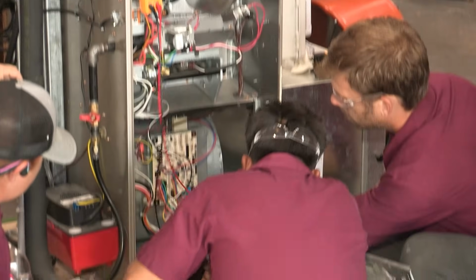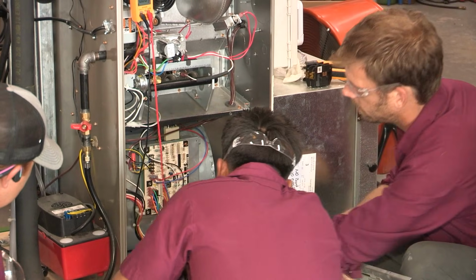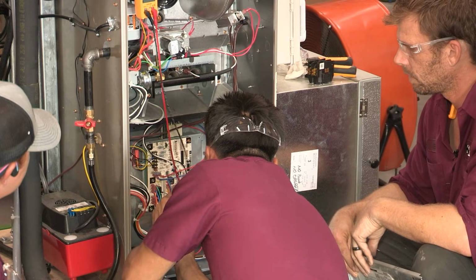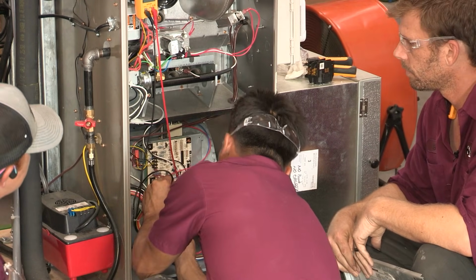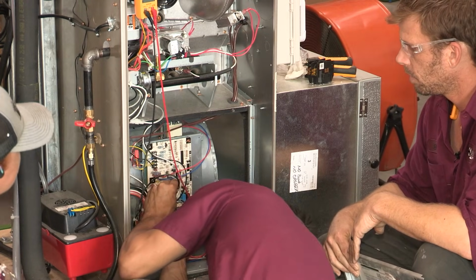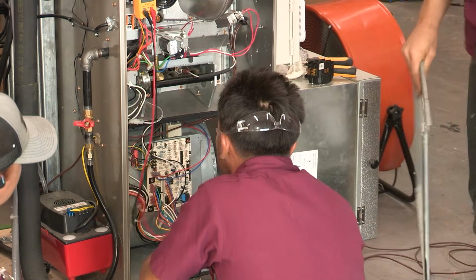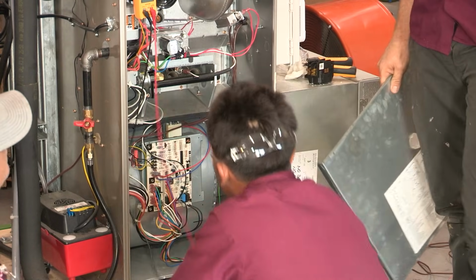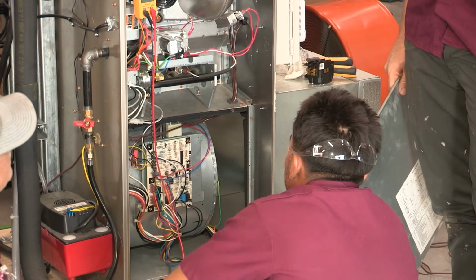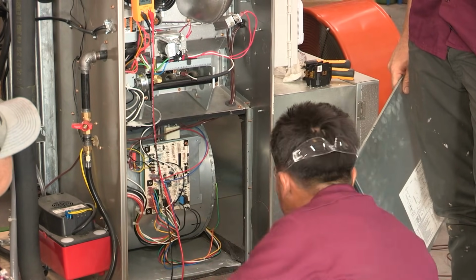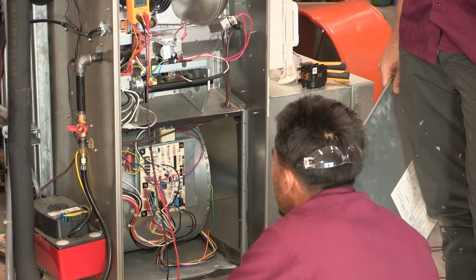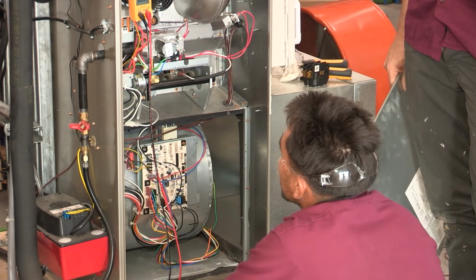Is that the bottom one? Yeah, it is, you have to come in from the bottom. To any neutral? Nope. Okay, so what have we learned so far? We're not getting power to the board. Yep, we're not getting power to the board, and we're not getting power to the transformer, so we don't have power to our 24-volt generator, the transformer.